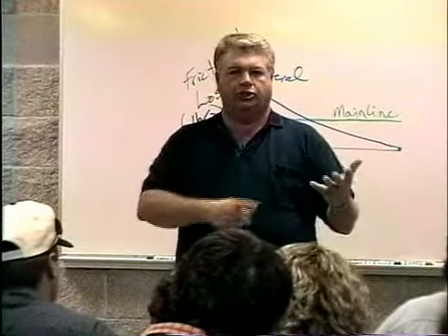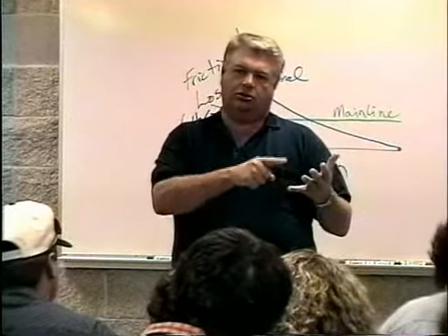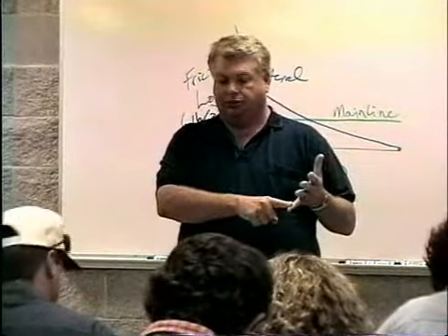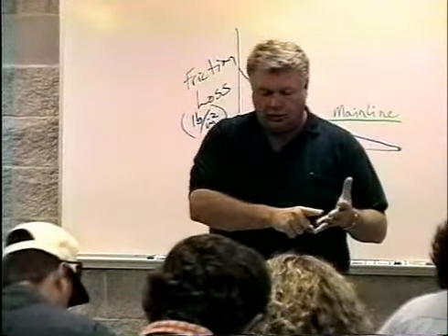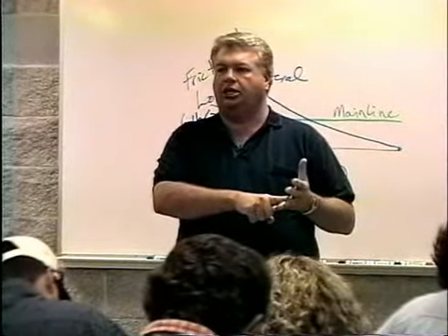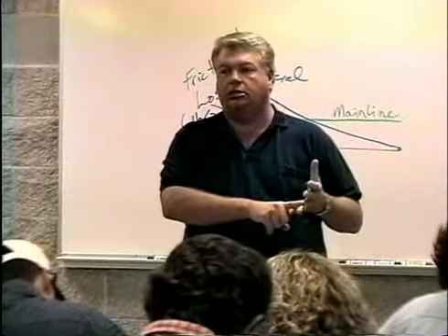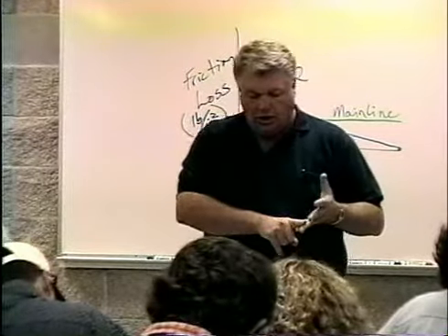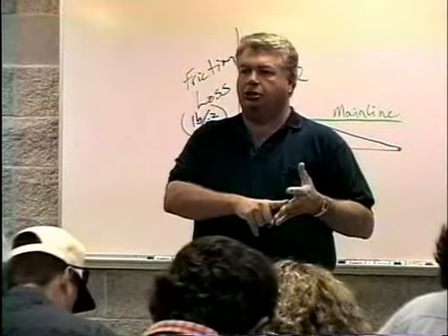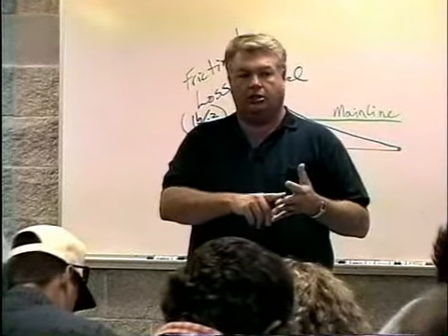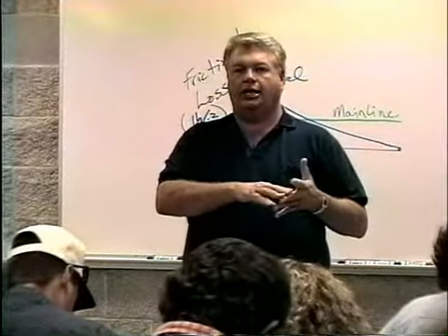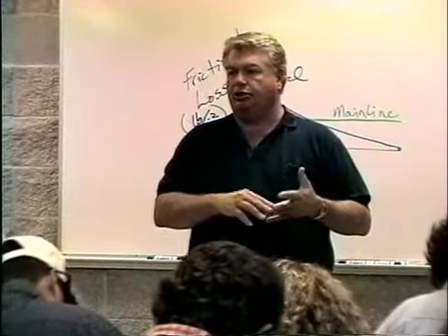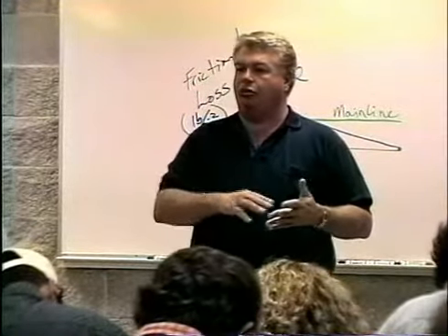So we have a few things to overcome. We have to overcome the pressure of the nozzle, what we call the exit pressure. We have to overcome the friction in the main line and the laterals and all of the fittings, valves and so on that are included in there. We have to overcome the elevation differential. That could be a plus or it could be a minus. If it's going downhill, we gain power back. It's work the pump will not have to do. We can subtract it from its energy. If it's going uphill, we have to add more energy.